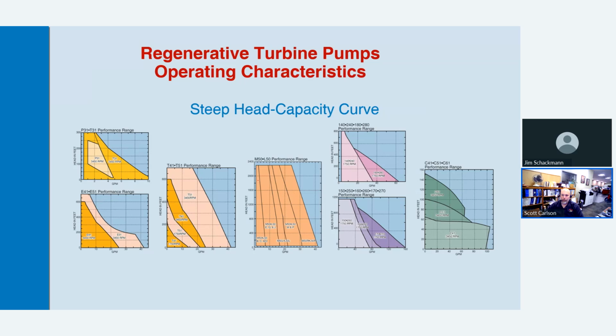The first thing to know about regenerative turbine pumps is that their main characteristic is a steep head capacity curve. They're higher pressure than they are flow, which is the opposite of a centrifugal pump, which is known for its flow and not necessarily its high pressure.